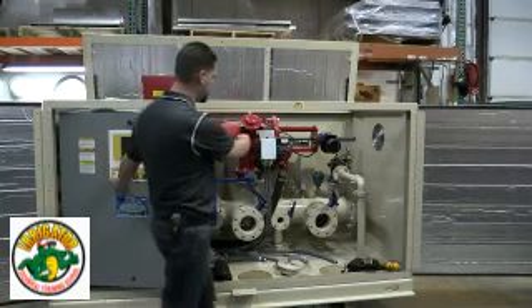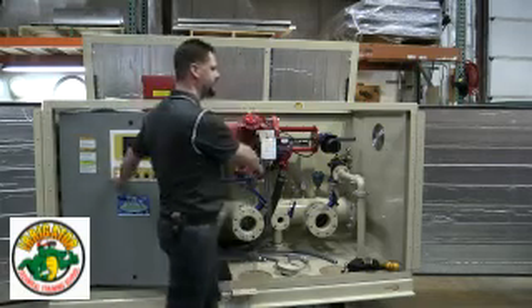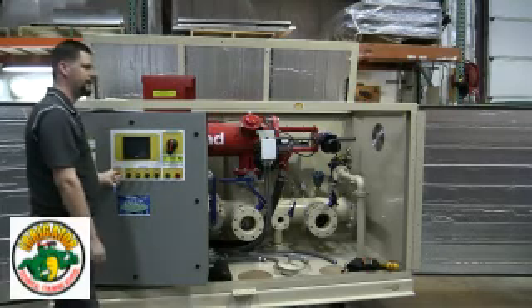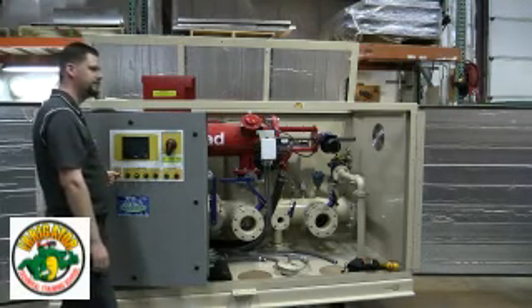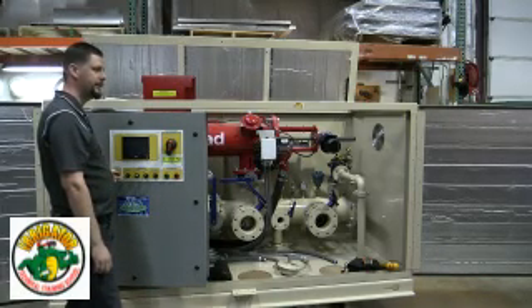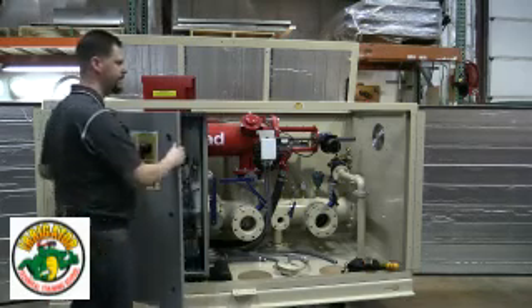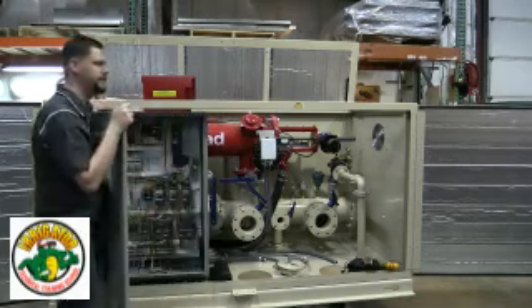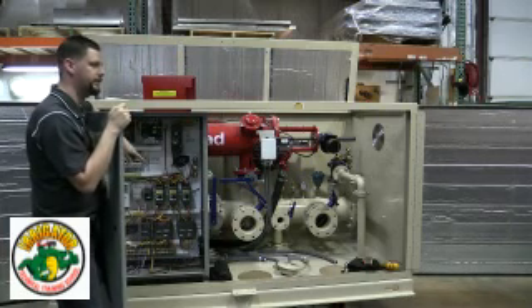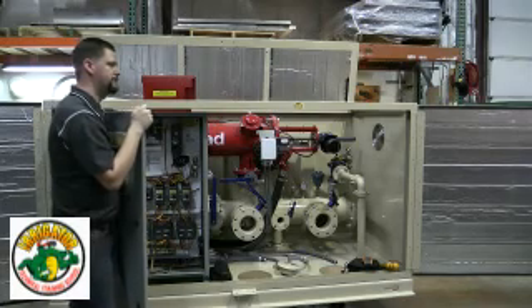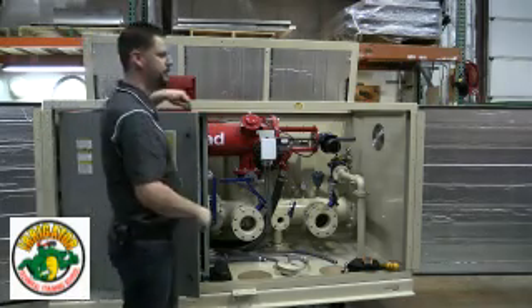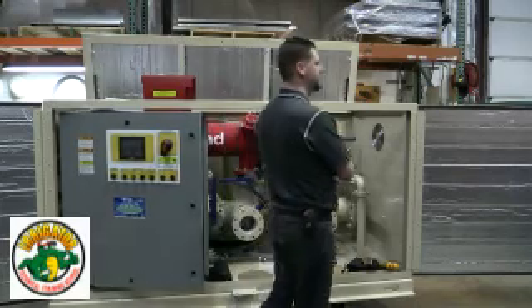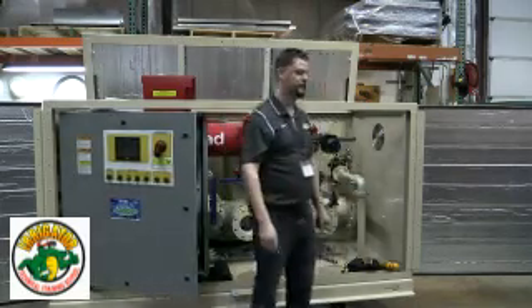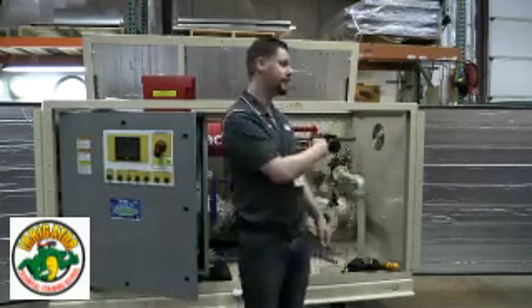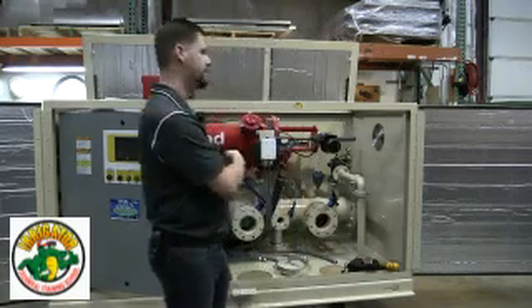Now, what I'm looking for is when the pressure switch is going to close. So if we get it up there past where you think it should shut, and you're not getting any indication, you may have to throw your meter on there, test for continuity or voltage on the return wire to ground. Just to make sure, because not all of our systems shut down on high pressure in hand. Just the way it is. Otherwise, you can raise the set point in auto, but make sure that isolation valve is shut.